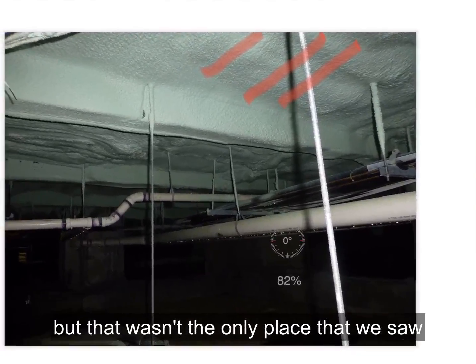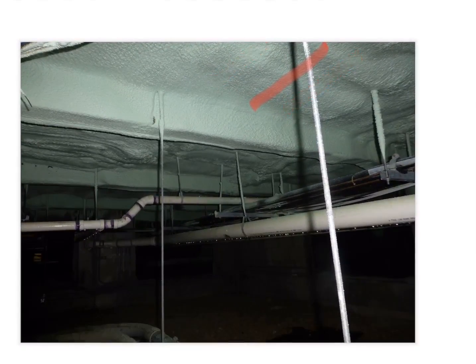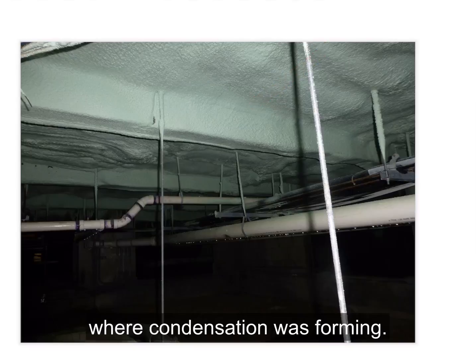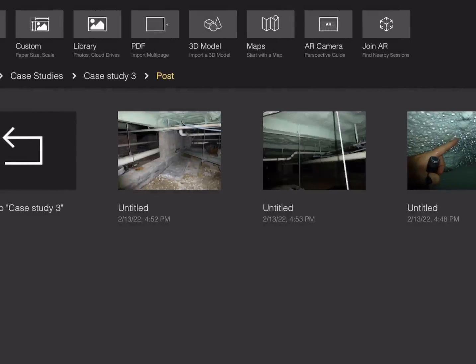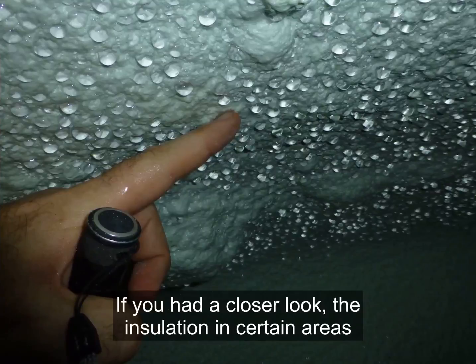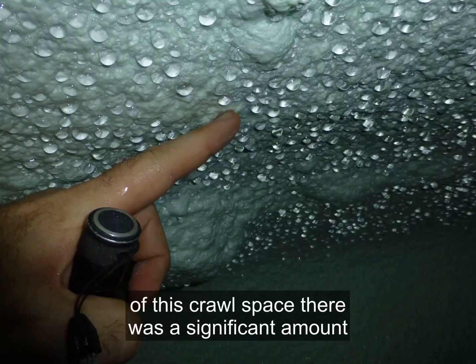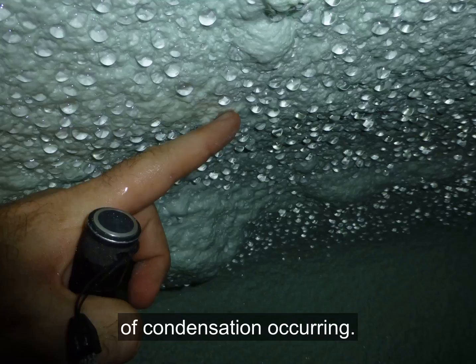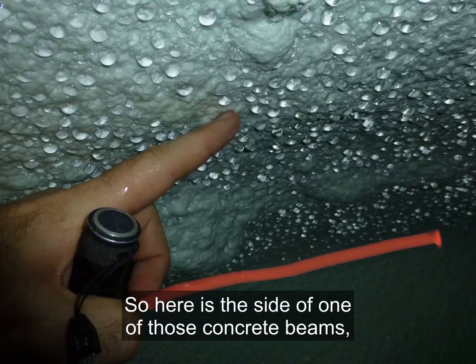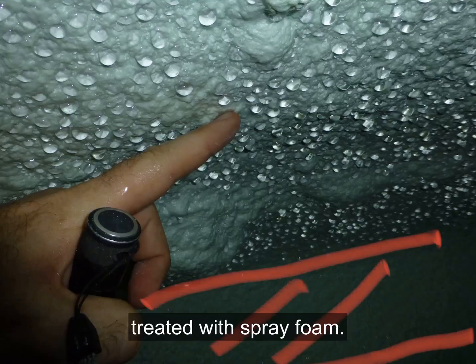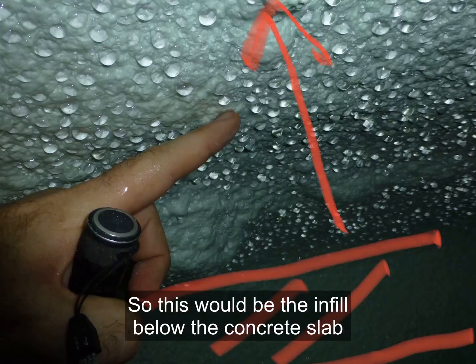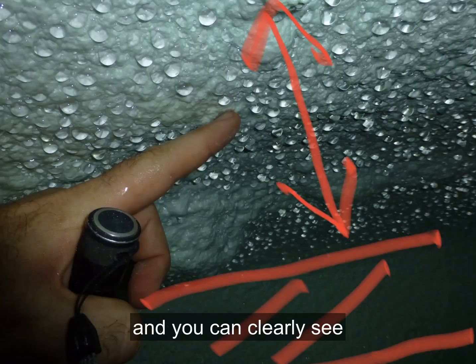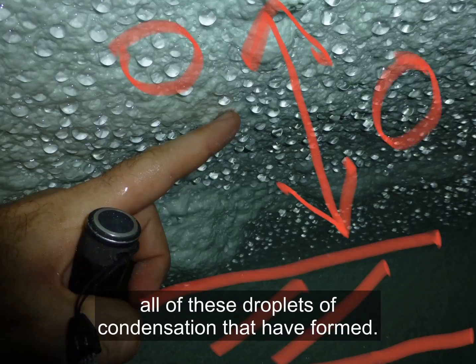But that wasn't the only place that we saw where condensation was forming. If you have a closer look at the insulation in certain areas of this crawl space, there was a significant amount of condensation occurring. So here's the side of one of those concrete beams treated with spray foam. So this would be the infill below the concrete slab, and you can clearly see all of these droplets of condensation that have formed.